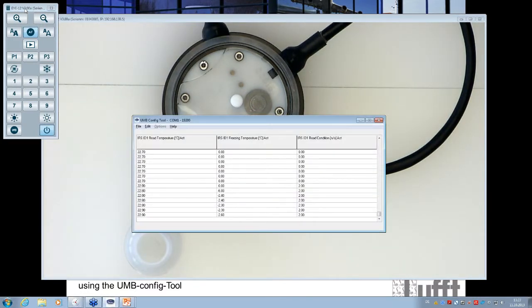And we go back to the UMB config tool, and hooray, you see that? That's great, because again, it depends on the outside temperature. And you see we have 22 degrees here. Normally it should be a bad value, but the sensor here is a very good one with a very good measurement. So you will see the freezing temperature normally should be -2, right? The sodium chloride which we use is -2, and you see it's -2.7, which is not so bad. Normally it would be better if we have an outside temperature of maybe 5 degrees, or the best would be 0 degrees. Okay? And now you have also checked the freezing point measurement. Now you can of course use the second fluid to check also the -10 degrees freezing point. No problem, but you will see it's okay here, right?